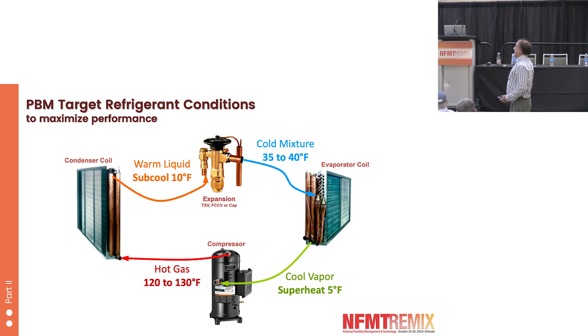Okay, so let's see what else we got. Warm liquid, subcooling 10 degrees. So if you see your subcooling isn't 10 degrees, maybe it's only 2 degrees, that tells you you've got something wrong with your condenser, that it's fouled, needs cleaning, maybe the fan is not turning as fast as it should be. Anyway, some investigation there. And then along with the refrigerant temperatures and refrigerant deltas, there are air temperatures and deltas that are sort of optimal. And again, these aren't hard numbers, like the condenser split, I put 10 degrees, but if it's 8 degrees or 12 degrees, it doesn't have to be exactly that. The thing is, if your condenser split is like 15 or 20 degrees, then you've got a real issue.